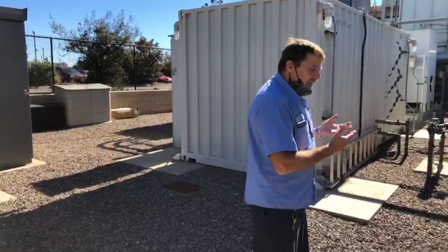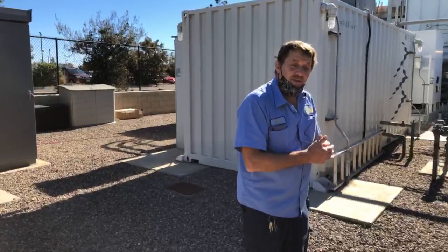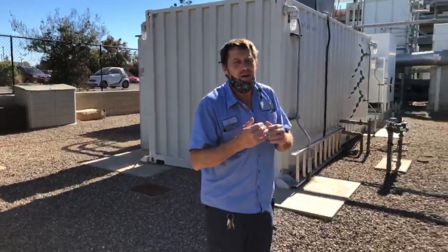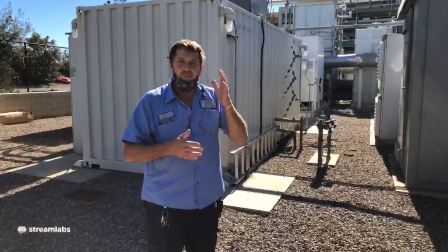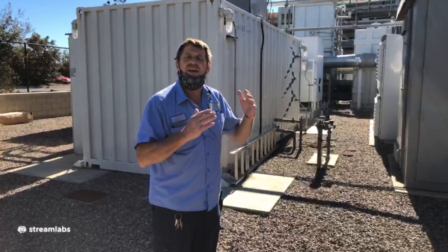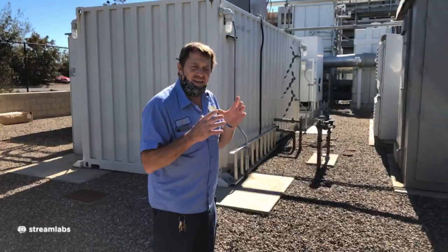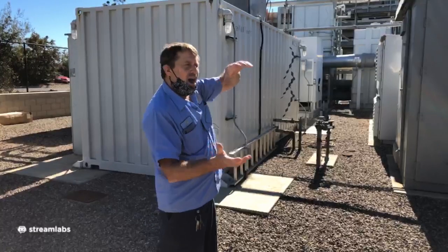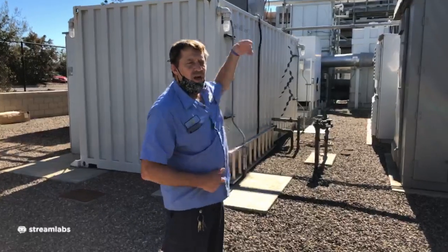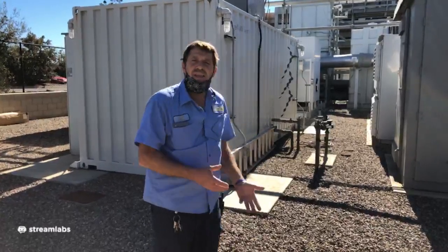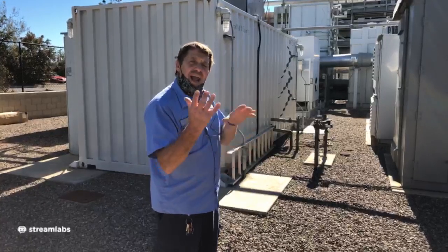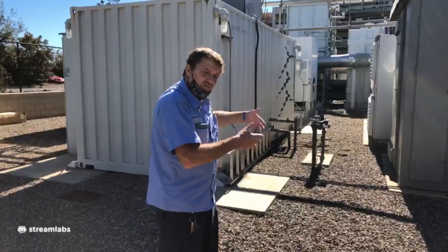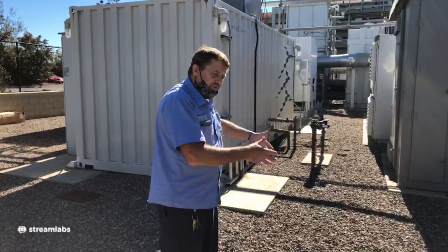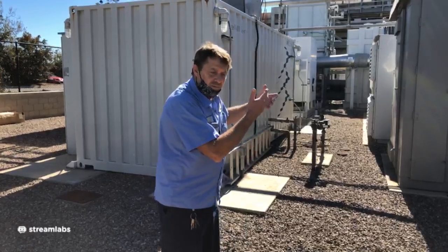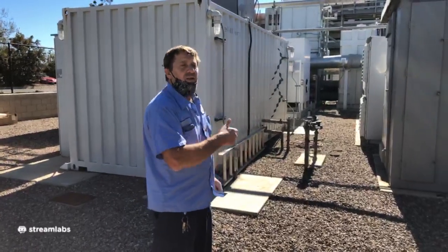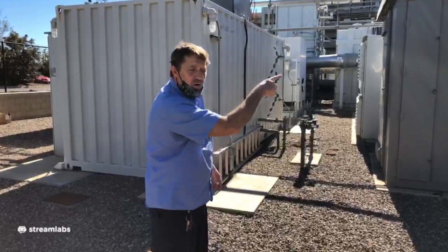That's science. And the heat that comes off of it, this is the interesting part that I know a little bit about. The heat that comes off of it is somewhere between 700 and 800 degrees. And then that heat, in the form of hot gas, goes into an absorption chiller, a lithium bromide absorption chiller, and that heat boils the refrigerant, and then the refrigerant is able to make the cold water, the chill water that we make for the system.